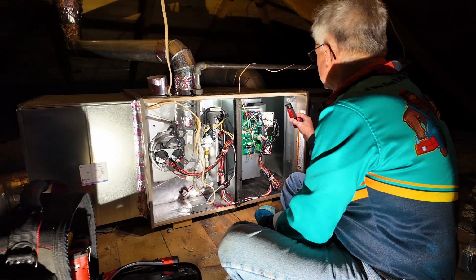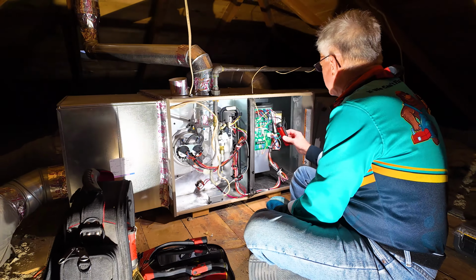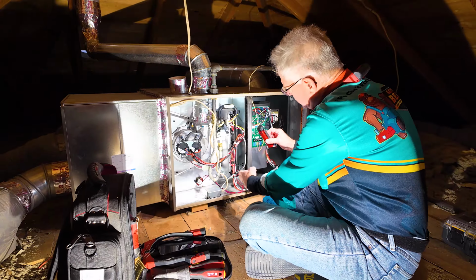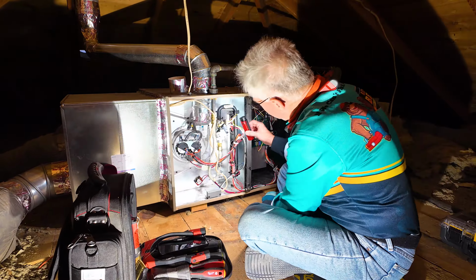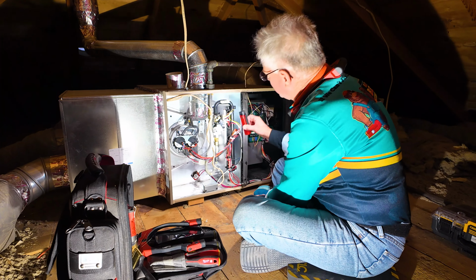So I'm basically going to just take a look at everything and then identify where the burners are, and the burners are of course right here. So I suspect that it's the flame sensor, and the flame sensor is right back in there. I don't know if you can see where I'm pointing, but that little thing there is the flame sensor, and then up here is the igniter. When the furnace turns on, after it goes through a safety sequence and checks all the safety devices, it'll actually come over here and turn the gas valve on.